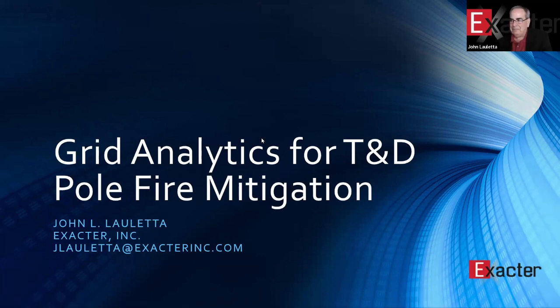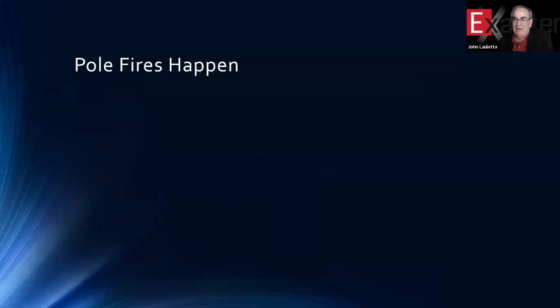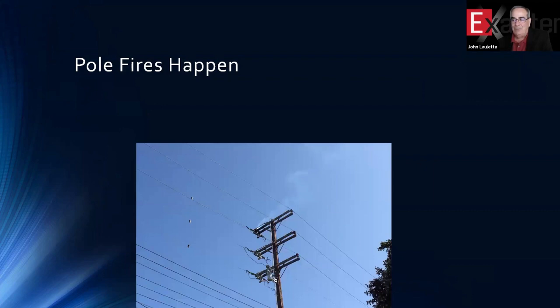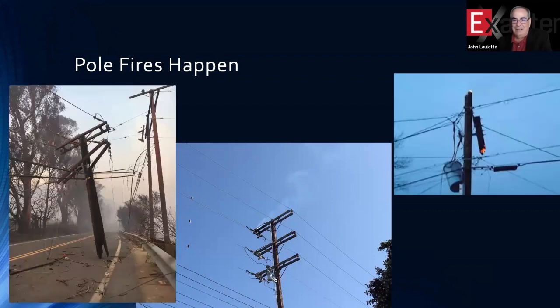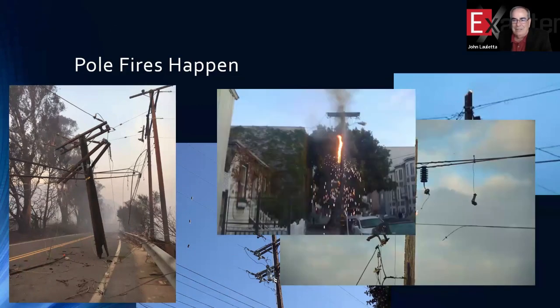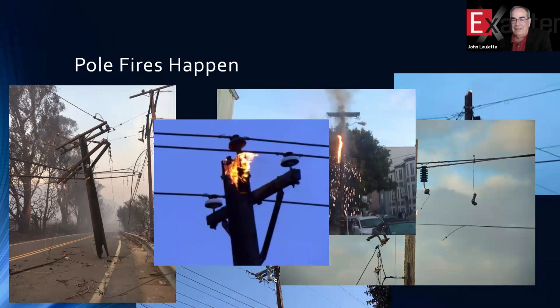So we'll begin with just the idea that in fact pole fires just happen, and a lot of people say that it's one of these things that you can't avoid. They're just there, but that's not quite true. The pole fire that occurs from normal operation and wear and tear of the grid happens because of a number of elements that occur prior to the actual event. And a pole fire may take a year to develop before it actually comes to fruition, where there's wood flaming or brush below the pole catching fire. So we'll look at all of this and see if we can't learn how this process begins and what we can do about it.